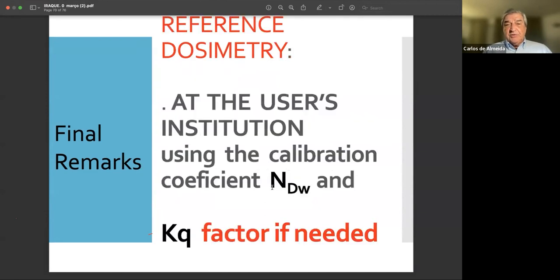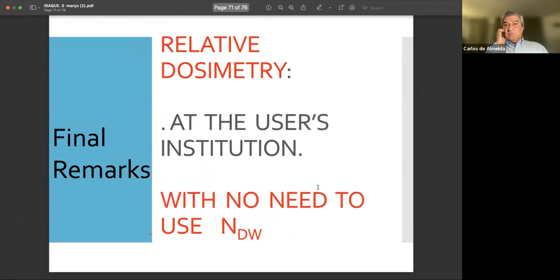Reference dosimetry is what we do in our institution. That's what you do in your institution, using the calibration coefficients. But you have to remember that the kQ factor may be needed if you're not using the same beam as the beam in which the chamber was calibrated. Next one. For the relative dosimetry in the user institution, there's no need to use the N_D,w. So as we mentioned, you can use several detectors as long as you keep track of the response of those detectors, keep track of the stability of the systems, and also keep track of the damage that may occur to those instruments.